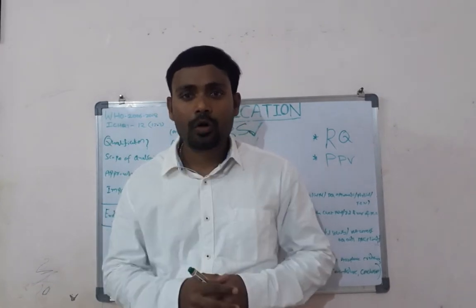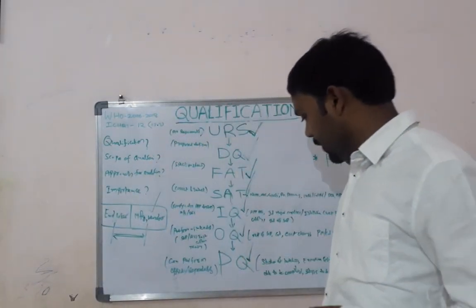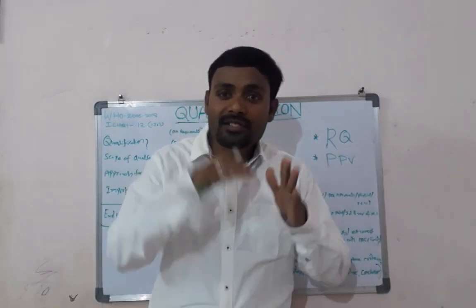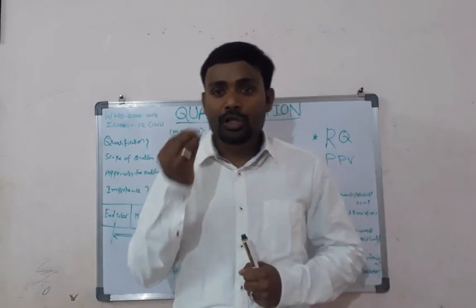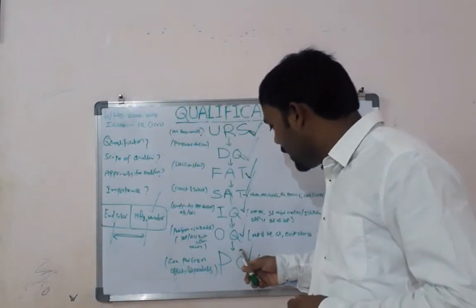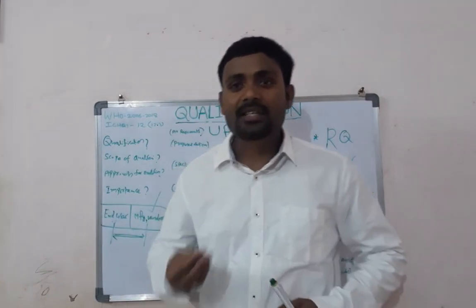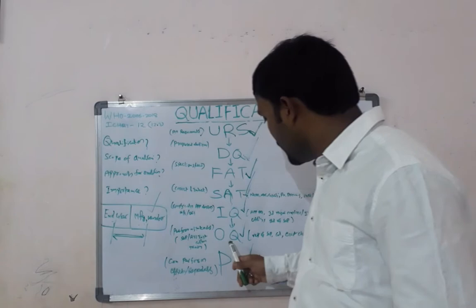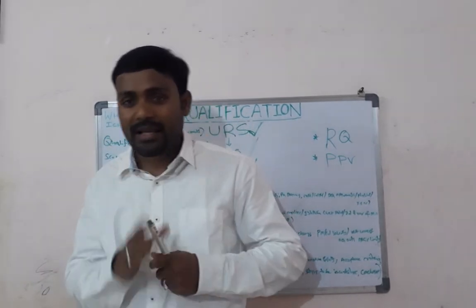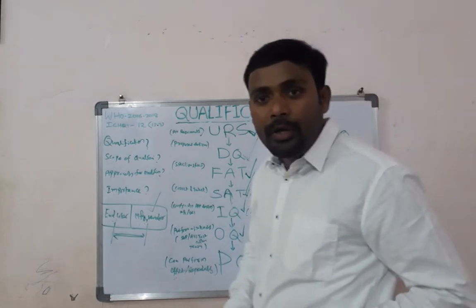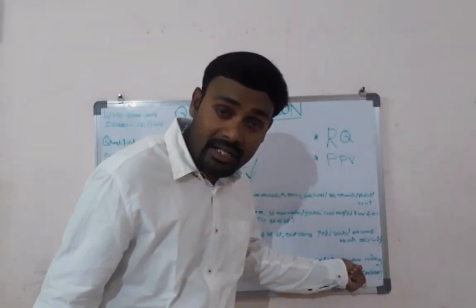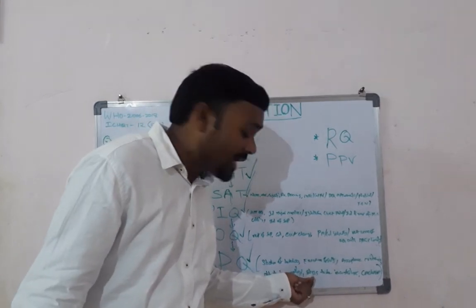Performance Qualification (PQ) is a documented verification that an equipment and its ancillary systems connected together can perform reproducibly and effectively with respect to the approved process method and specifications. In PQ, batches are selected to prove consistency, reproducibility, and repeatability of the equipment. The PQ protocol should include a detailed execution plan, acceptance criteria, and batch selection. The PQ report covers batch selection, execution outcomes, results, acceptance criteria, data compilation, failure steps, and final conclusion.